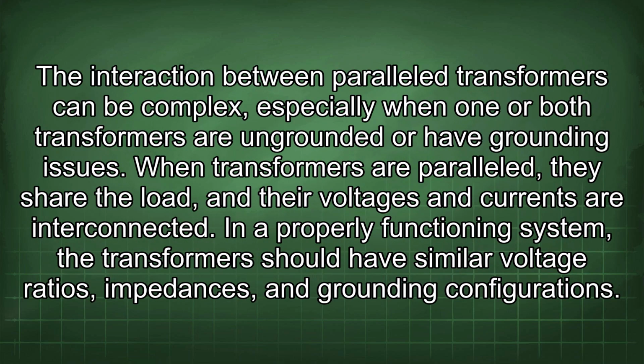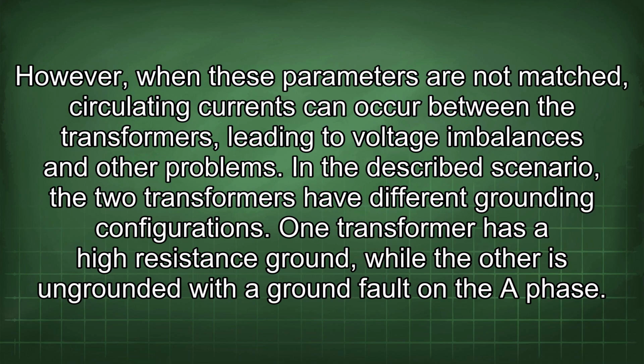The interaction between parallel transformers can be complex, especially when one or both transformers are ungrounded or have grounding issues. When transformers are paralleled, they share the load, and their voltages and currents are interconnected. In a properly functioning system, the transformers should have similar voltage ratios, impedances, and grounding configurations. However, when these parameters are not matched, circulating currents can occur between the transformers, leading to voltage imbalances and other problems. In the described scenario, the two transformers have different grounding configurations.